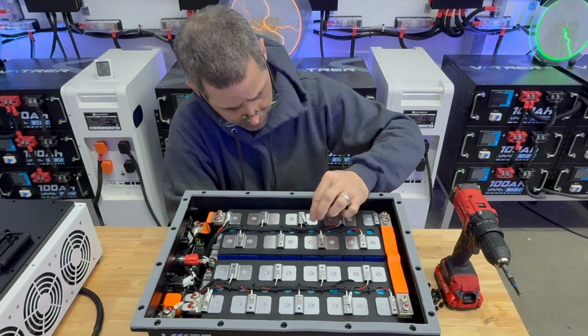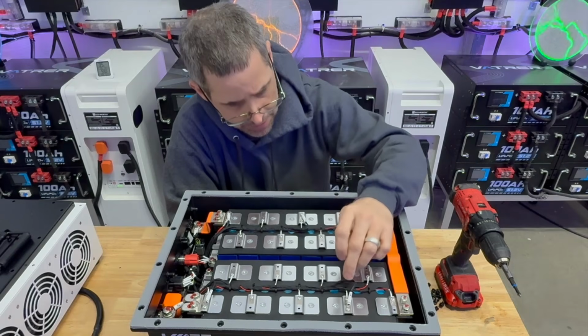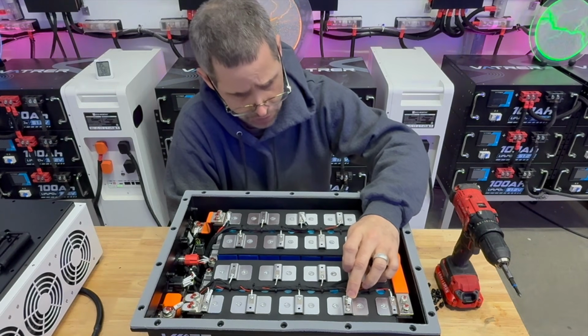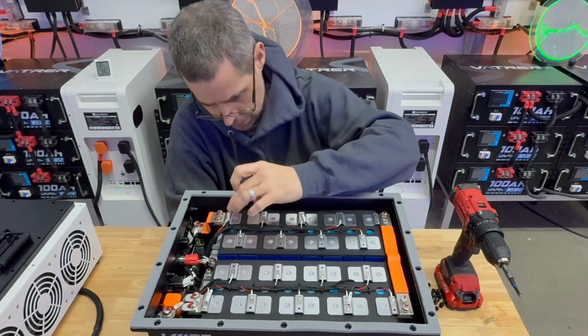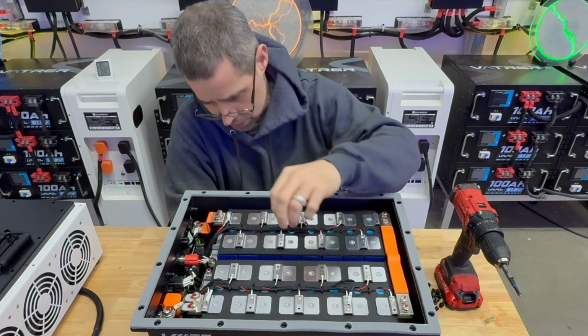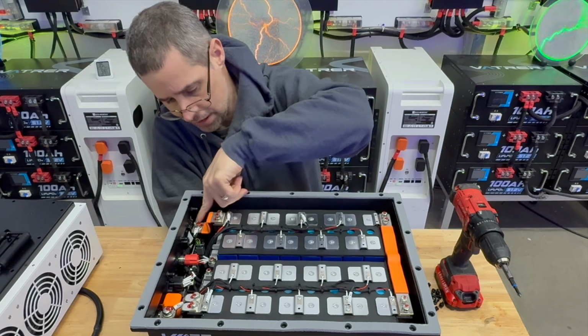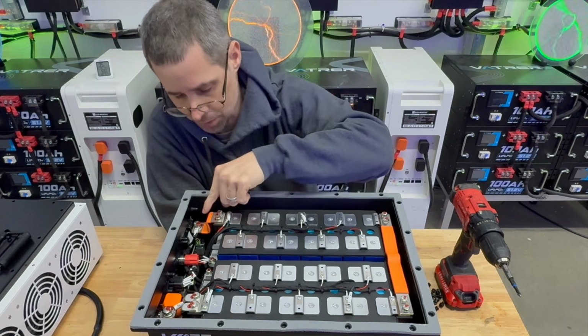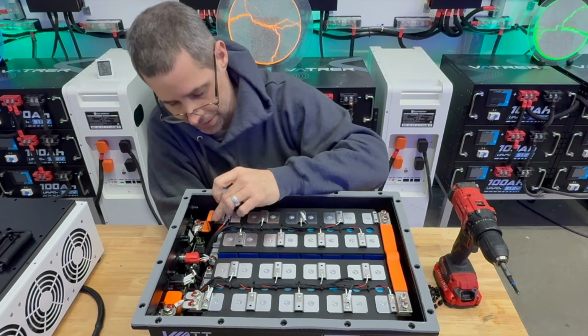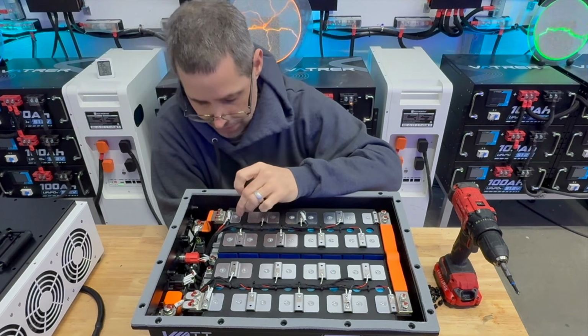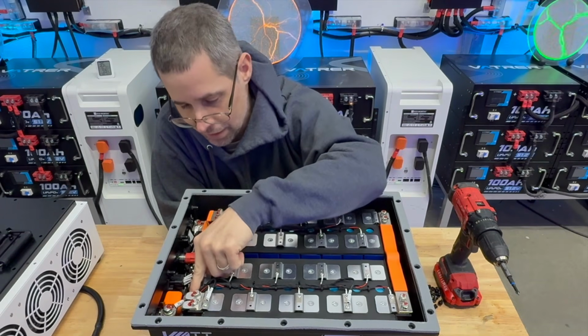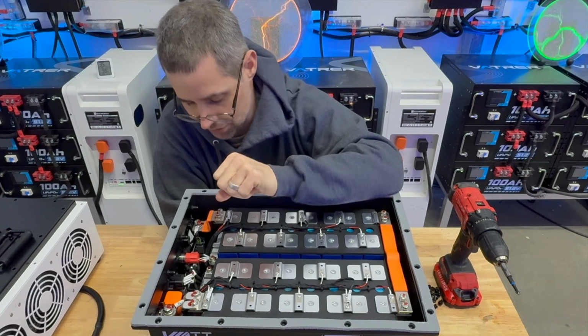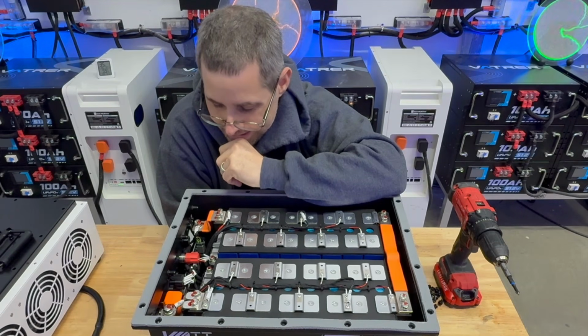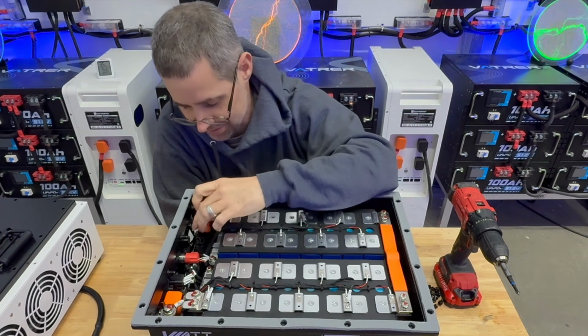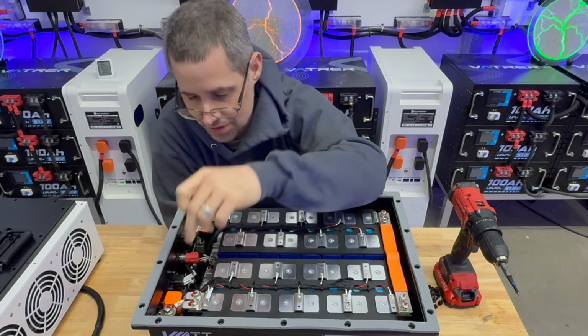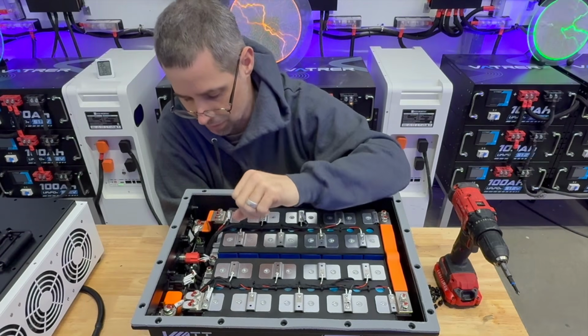There are temperature sensors—one on this side, another on this side. Actually, there are 4 temperature sensors: 1, 2, 3, and 4. And that's kind of nice. What I like about this is you can see the bus bar that connects to the terminal, and they've got one of the temp sensors right there, so if there's any excessive heat it's going to pick up on that. But wait, there's more—another temperature sensor actually on the connections. That is cool, I like that. So it actually has 6, very nice, T5 and T6. So it's got 6 temperature sensors, and 2 of them are on the bus bars.